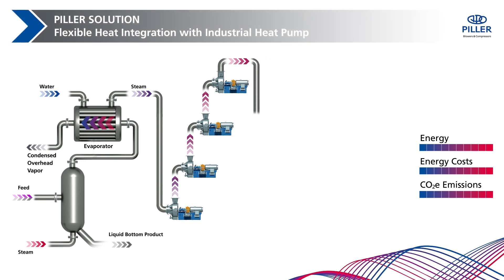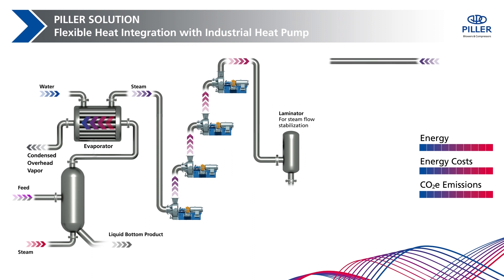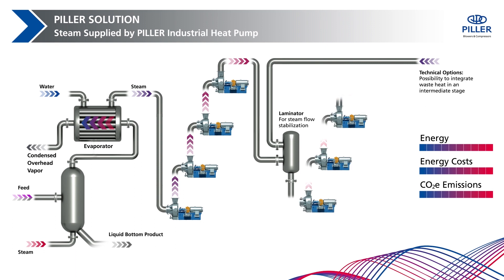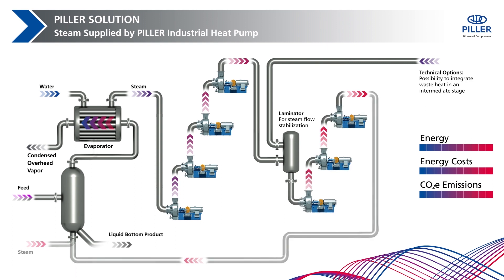The multi-stage arrangement of Piller blowers opens the system to integrate additional waste heat sources. Excess steam, like flash vapor from other processes, can be combined with the freshly generated steam in a laminator. This flexibility of integrating other sources at any intermediate stage allows even more heat recovery. Feeding the compressed vapor back into your process or into a steam network preserves energy and reduces greenhouse gas emissions.